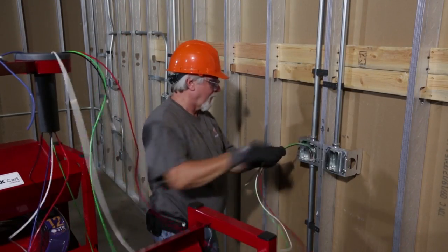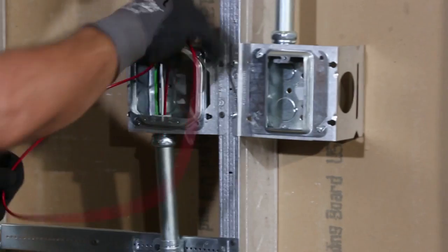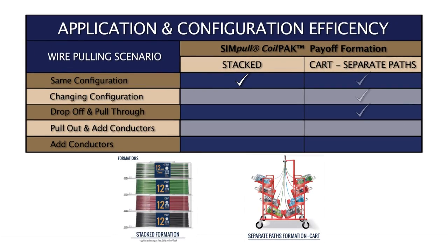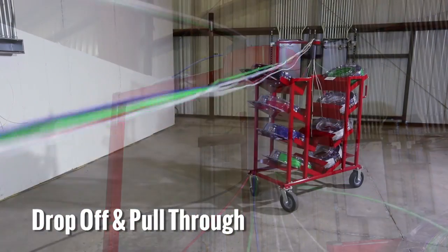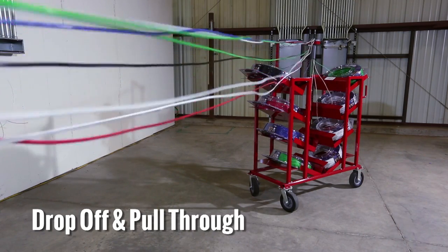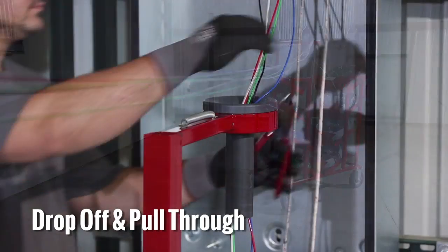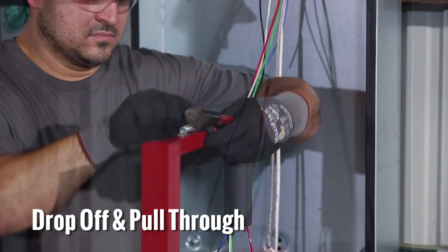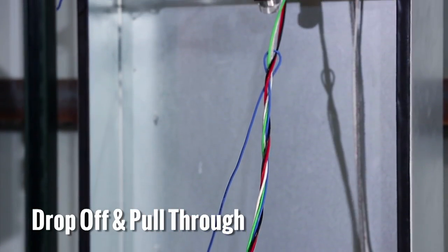In applications where you'd like to drop off a conductor or conductors in a box and pull through to the next box, the SIMpull CoilPAK cart is the most efficient arrangement. The separate paths allow the rest of the conductors to pull smoothly from the SIMpull CoilPAK payoffs with minimal effort and no tangles. With stacked configurations, the conductor twisting effect will likely pull the conductors along, making drop offs nearly impossible.